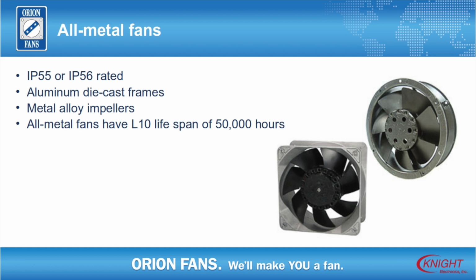Available with lead wire or terminal connections, the all-metal fans have an operating temperature range of -30 degrees Celsius to 80 degrees Celsius. The all-metal fans produce airflows of 18 CFM to 1,130 CFM in packages ranging from 80 mm to 280 mm in standard voltages of 115 volts AC or 230 volts AC.